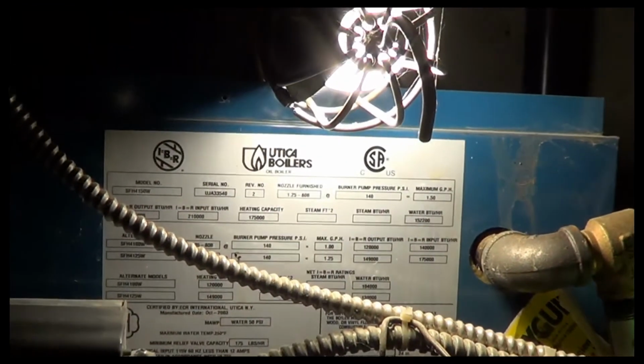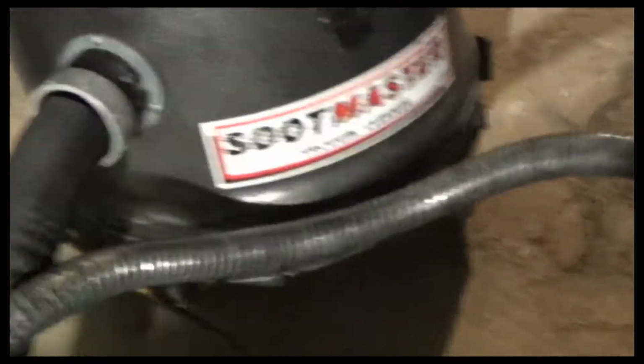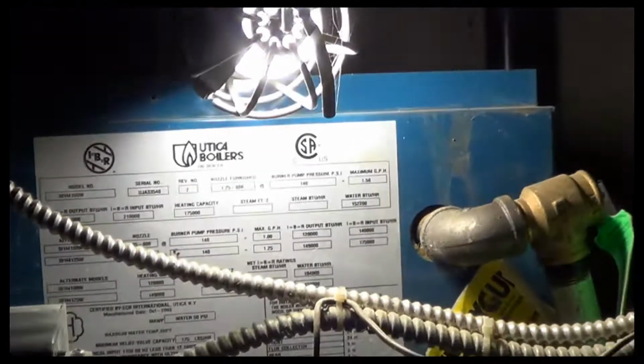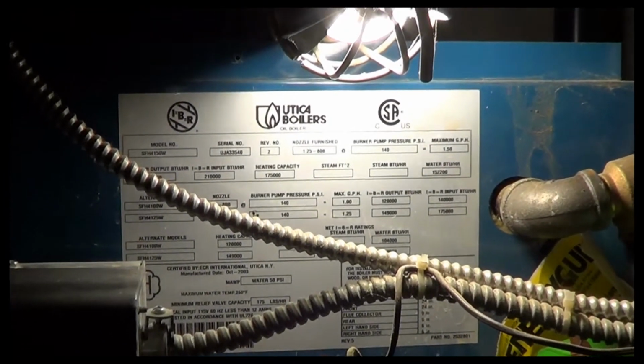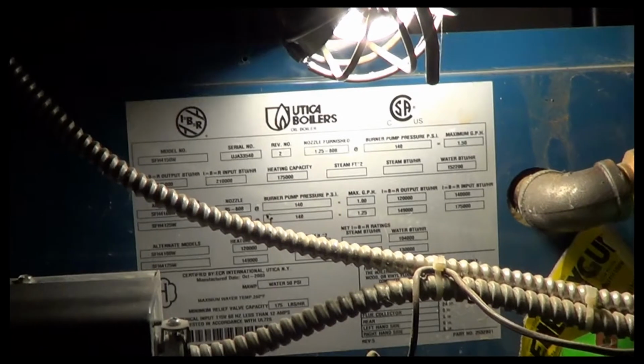Make sure everything's clean though. These people are paying good money for a cleaning and they expect good service. For the homeowners watching this, if somebody walks on an oil job and doesn't bring a soot vac in, they're not doing the right job. A lot of people around here just change the nozzle and filter, leave, and bill you the same amount I'm going to bill you. They don't even own a combustion analyzer, which is the most important part of the job, and they don't clean out your heat exchanger and flue pipe. It's got to be done. Make sure you're checking these things. I'll get back with you when I'm done and show you the printout. For now, I'm out, see you soon.